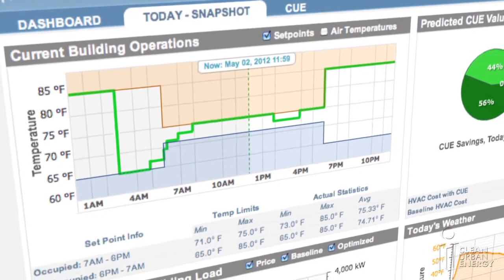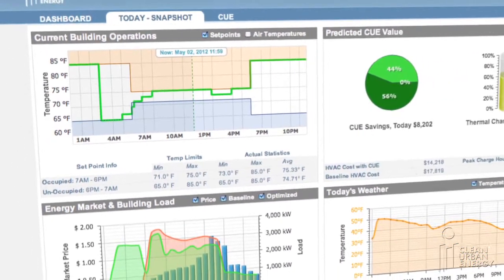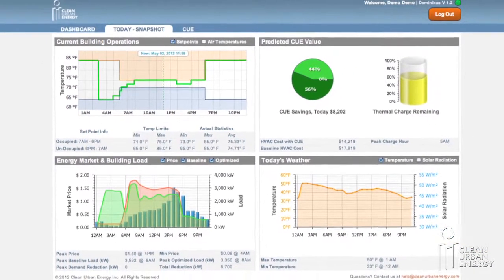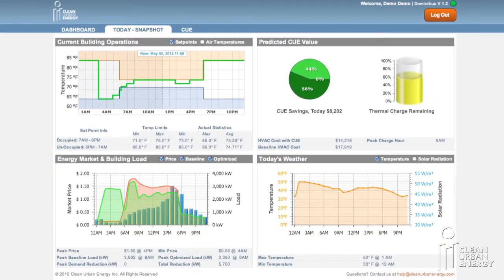We send a building 24-hour set points every day, every hour. This allows us to look 24 hours into the future and understand how the building should best operate. If energy prices go up, for example, that information goes into their building automation system and they can adjust operation in real time.